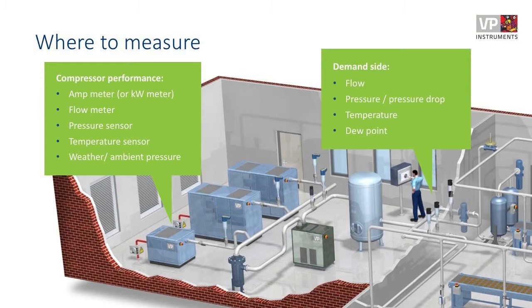A pressure sensor shows the overall pressure, but also lets you find pressure drops over the air treatment. A temperature sensor can also be very interesting because you can find issues with the compressor cooling system itself. You can also find issues with desiccant dryers and refrigerant dryers if you look at the temperature difference between input and output of the dryer. Ambient pressure is also a good thing to log, especially if you have, again, centrifugal machines. Different ambient pressure will result in different performance. That doesn't mean that the compressor is bad, it might be just the weather.